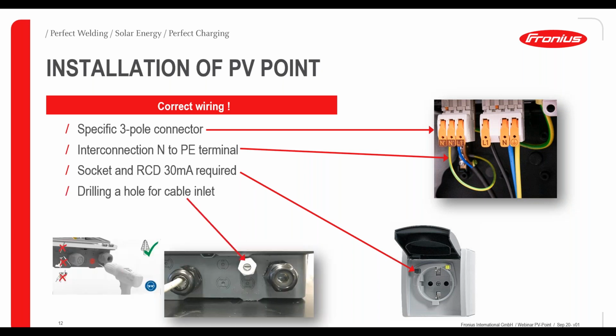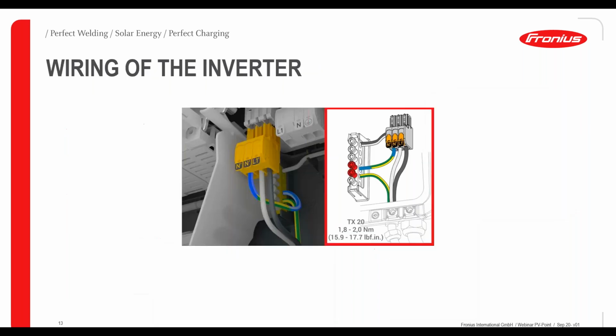The cable outlet or inlet will need a drilling hole, and you then get your cables out here on this white cable inlet. That's all you need to do, basically. And then again here, the wiring of the inverter. You see here the neutral connection to ground to make the RCD work, because on the RCD we measure the ground current. Therefore, we need that.